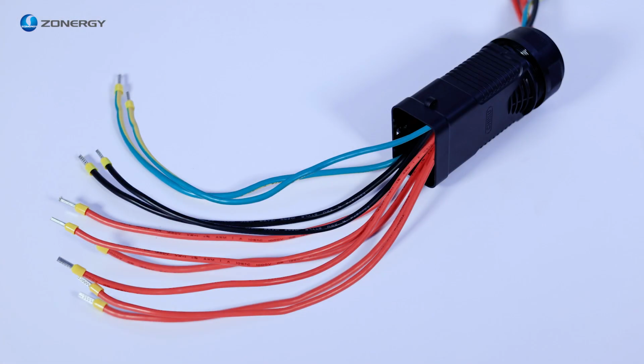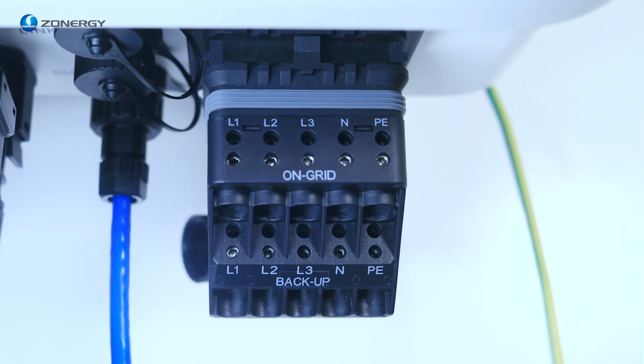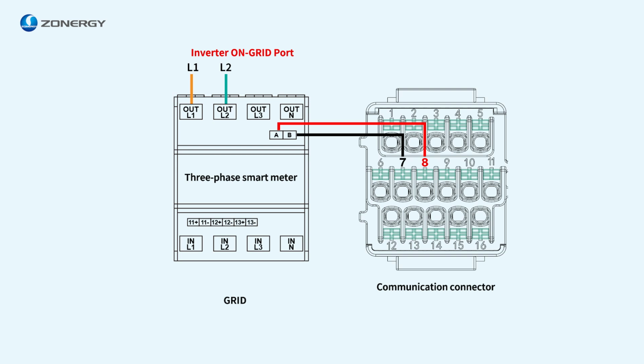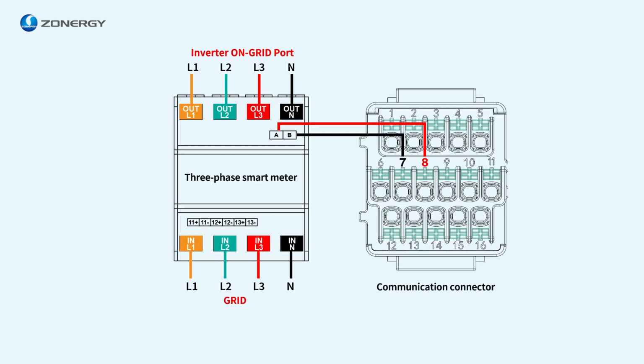6. The following are the threaded AC terminals. 7. Confirm the on-grid and backup of AC ports. On-grid is connected to the mains port. Backup is connected to the load port. 8. L1, L2, L3. End of the on-grid of the inverter should be connected to the out end of the intelligent 3-phase electricity meter, and the cables of the GRID correspond to the IN end respectively.